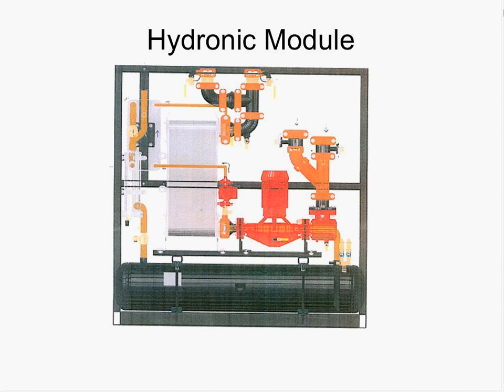On the side of it, you have the glycol coming in here and out here, and you have the end for the glycol to go to a fluid cooler or to a heat reclaim system, as controlled by some valves. And what we're using is two valves, opposing each other, to simulate a three-way valve.